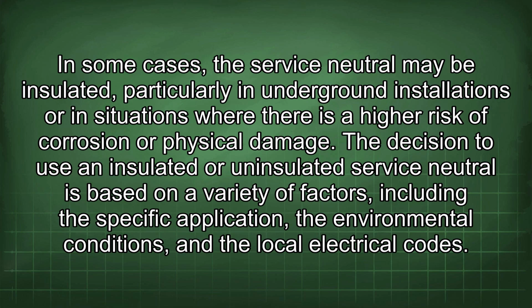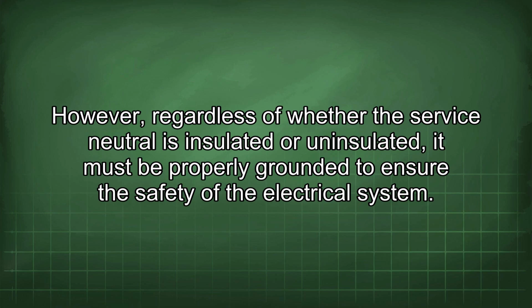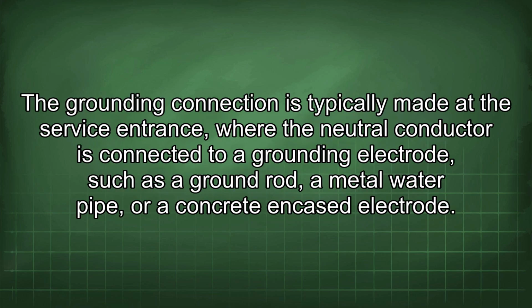The decision to use an insulated or uninsulated service neutral is based on a variety of factors, including the specific application, the environmental conditions, and the local electrical codes. However, regardless of whether the service neutral is insulated or uninsulated, it must be properly grounded to ensure the safety of the electrical system. The grounding connection is typically made at the service entrance, where the neutral conductor is connected to a grounding electrode, such as a ground rod, a metal water pipe, or a concrete encased electrode.